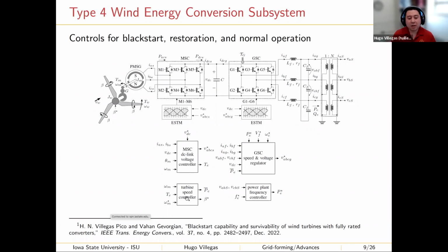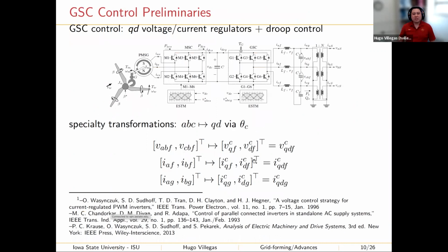So that is the communication happening here between the turbine speed controller and the grid side converter. Then we have a sort of virtual shaft to interconnect the grid side converter and the permanent magnet synchronous machine, and the turbine actually. In this presentation, I'm focusing on the grid side converter because it's relatively simpler, I think, to explain.